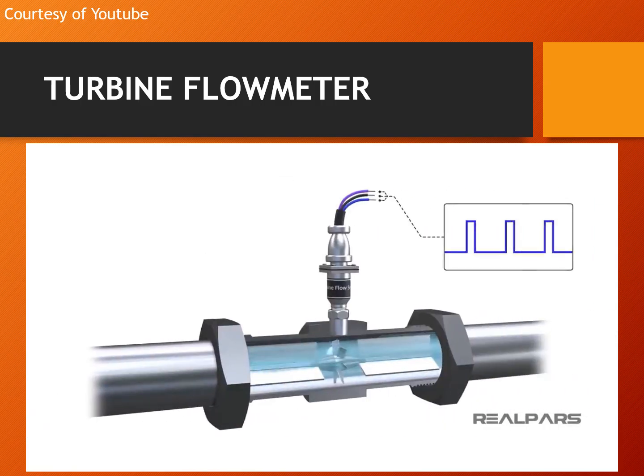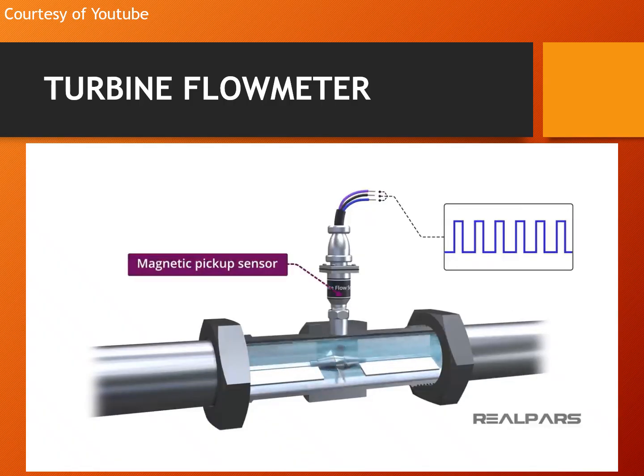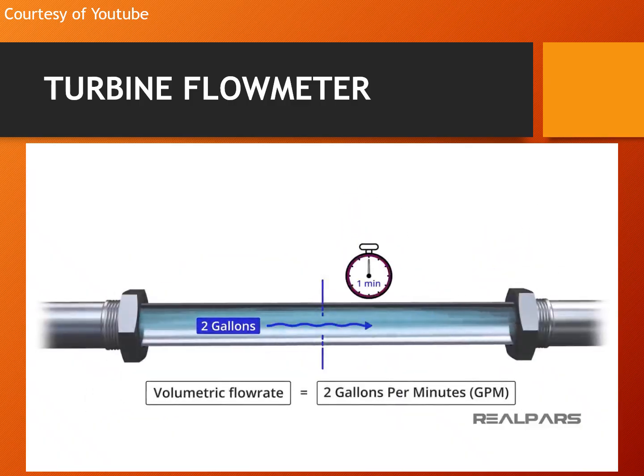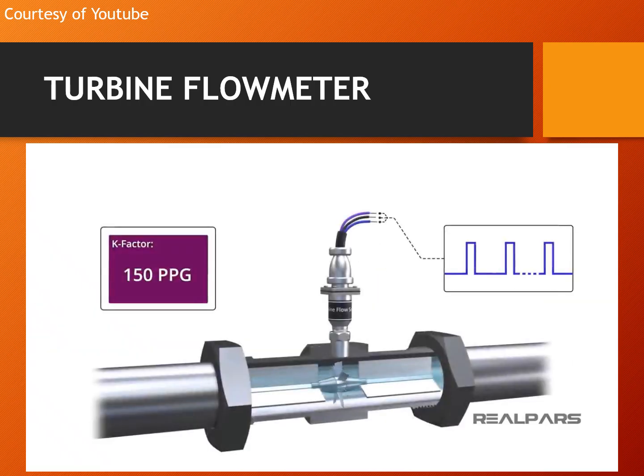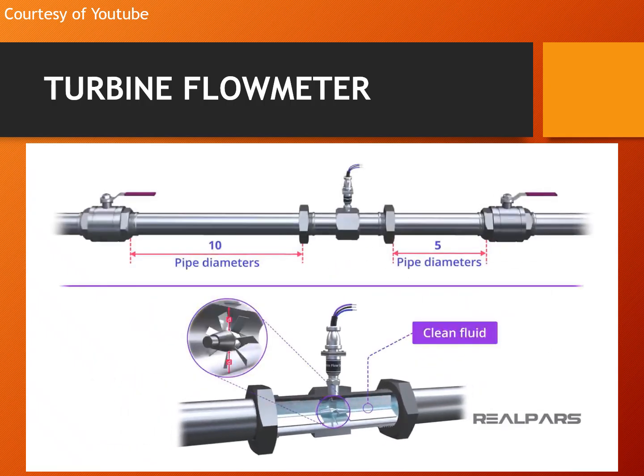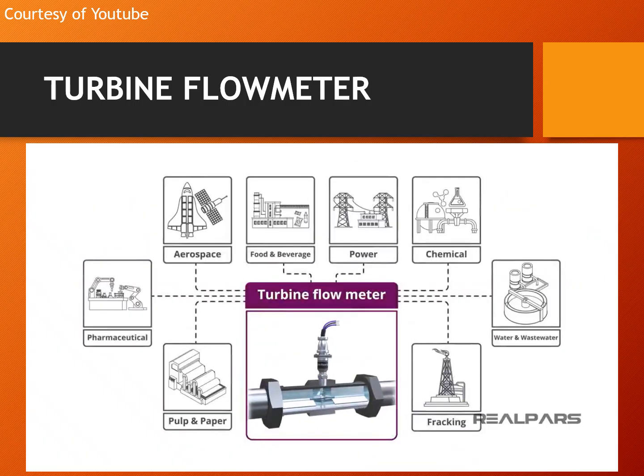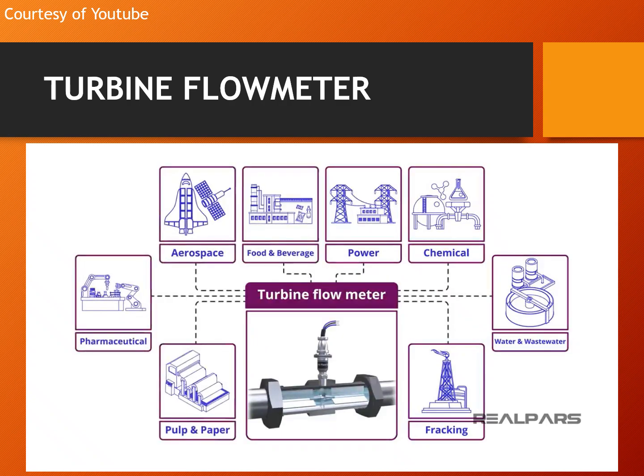Okay, let's review. A turbine flow meter is inserted in a pipe directly in the flow path and has a turbine rotor placed in the path of a flowing stream. The higher the rate of flow, the faster the rotor turns, and the greater number of pulses generated by an electrical pickup. In most applications, a turbine flow meter is used to measure volumetric flow rate. Every turbine flow meter has a unique K factor stating the number of pulses that will be generated for every unit of product passing through it. There are several important issues to consider when installing a turbine flow meter. Considering their popularity, there are very few industries where turbine flow meters are not used.